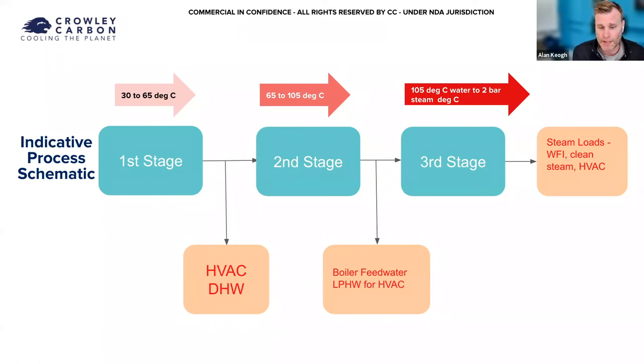So you can then use green steam because the heat pump is powered by green electricity. At the intermediate stages, you can draw off heat after the first stage and after the second stage to meet intermediate temperature requirements, such as some HVAC and AHU needs, domestic hot water, and potentially boiler feed water if you still have steam boiler requirements or a gas-fired steam boiler, plus LPHW for HVAC at around the 80 degree level.